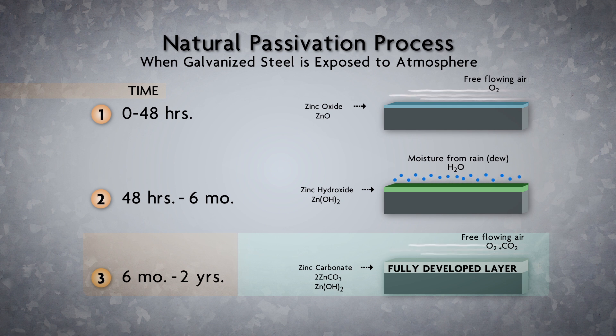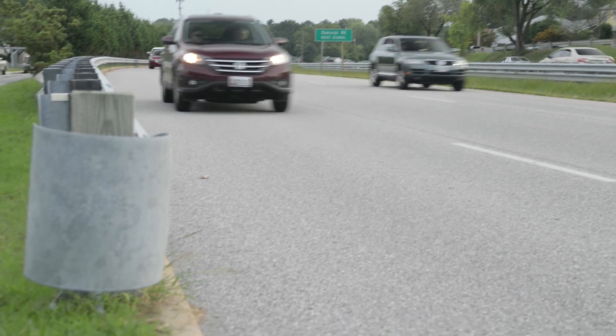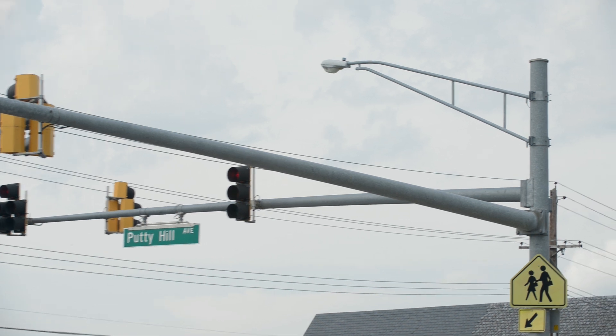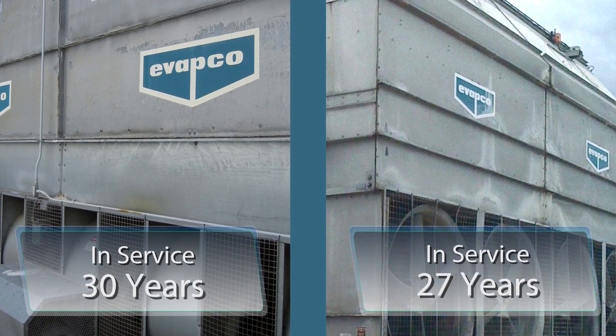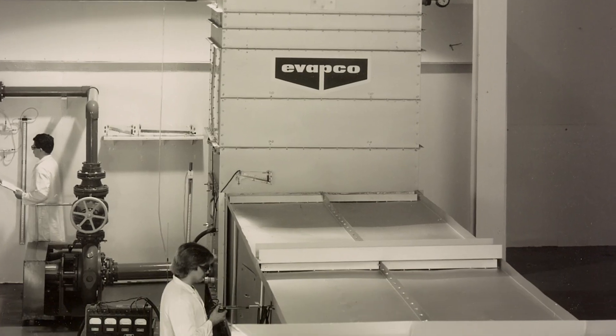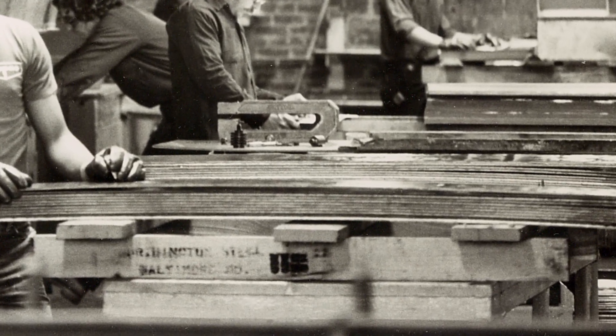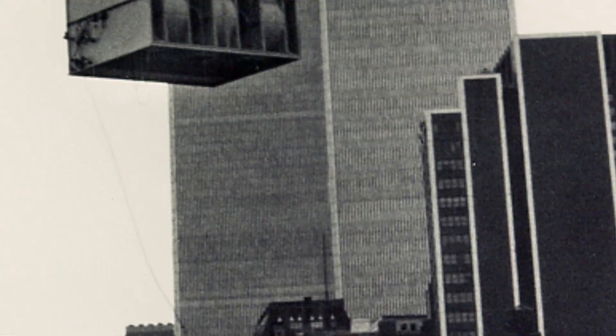The passive layer protects the zinc from premature corrosion. The fact that a passivated layer will naturally develop over time in air is one of the reasons why galvanized steel guardrails and lampposts, along with the outside casing of galvanized evaporative cooling equipment, rarely experience premature corrosion and have a long service life. With its ability to provide decades of corrosion protection when passivated and maintained, galvanized steel established itself as the go-to material of construction for factory-assembled evaporative cooling equipment throughout the 60s, 70s, and early 80s.